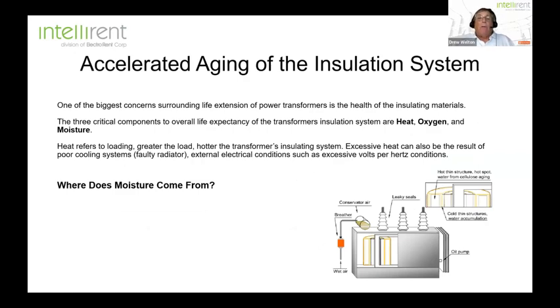Well, the first thing I want to discuss, and I've talked about this before, I make a big point of this because it is very important in terms of extending the life of a transformer. And that is the insulation system. Three things that really accelerate the aging are heat, oxygen, and moisture. And of course, heat refers to loading. The greater the load, the hotter the transformer's insulation system is going to be. Heat can also come from poor cooling systems, faulty radiators, or some outside electrical conditions, such as volts per hertz conditions, that can really heat up the windings of the transformer. But one of the things that we can certainly control is moisture.